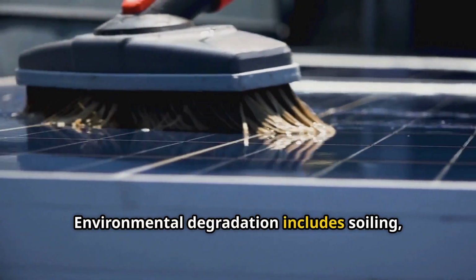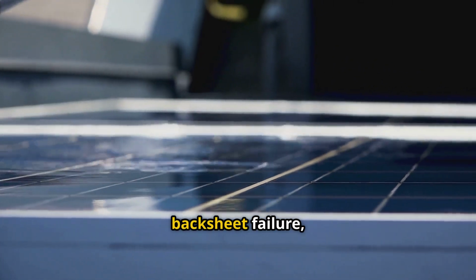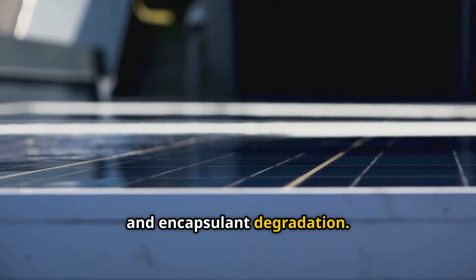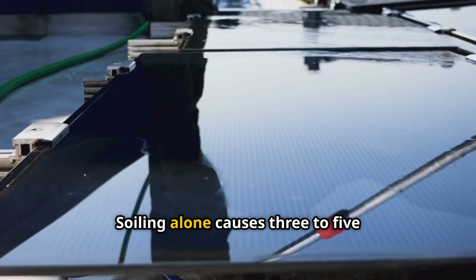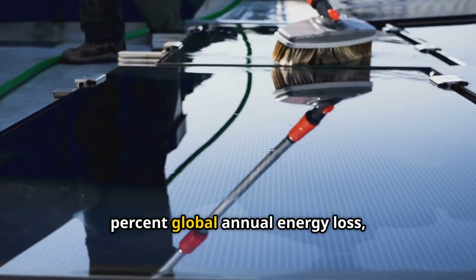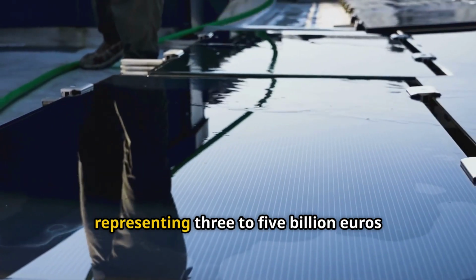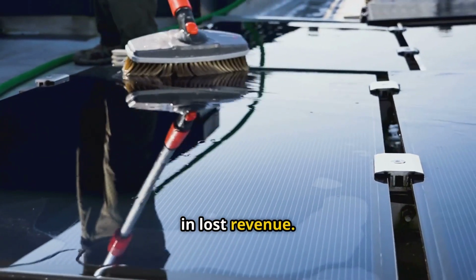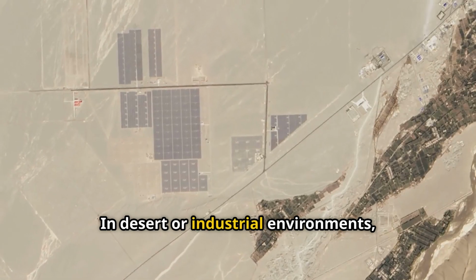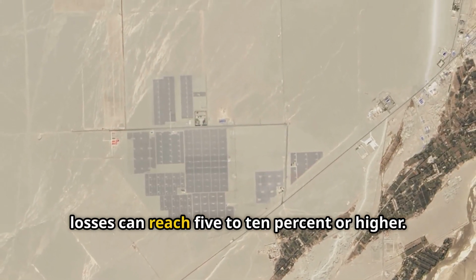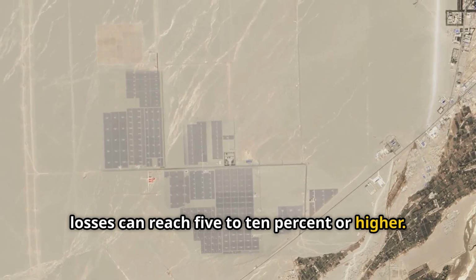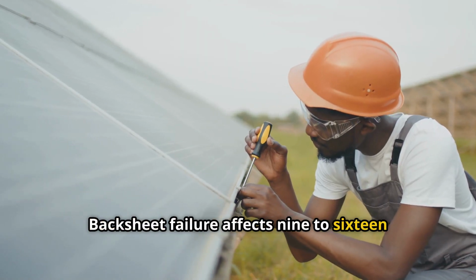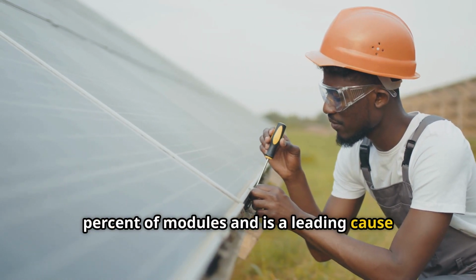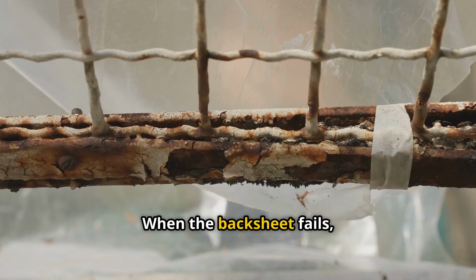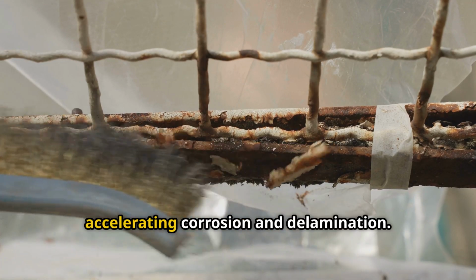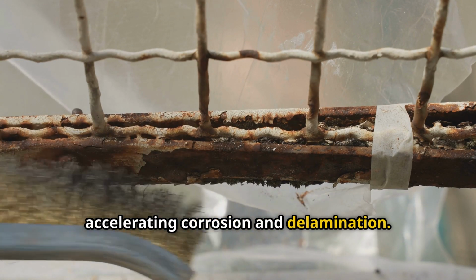Environmental degradation includes soiling, corrosion, backsheet failure, and encapsulant degradation. Soiling alone causes 3 to 5% global annual energy loss, representing 3 to 5 billion euros in lost revenue. In desert or industrial environments, losses can reach 5 to 10% or higher. Backsheet failure affects 9 to 16% of modules and is a leading cause of premature failure. When the backsheet fails, moisture enters, accelerating corrosion and delamination.